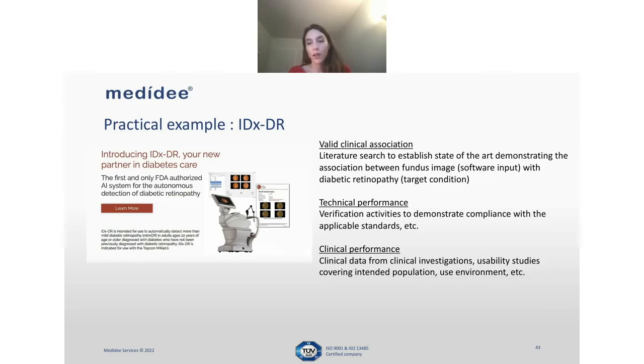Sometimes there might be some specific ISO that might be helpful. This is correct. And keep in mind also the harmonized standards by the EC. Precisely. Verification of the device's intended use, compliance with standards. I think intended use falls more into the validation, validating that for its intended use, the device is performing clinically correct. Verification is more that the device has been developed as it should be, that it complies with the various standards, that it meets certain thresholds for performance, etc. This is something that you look at with clinical evaluation.